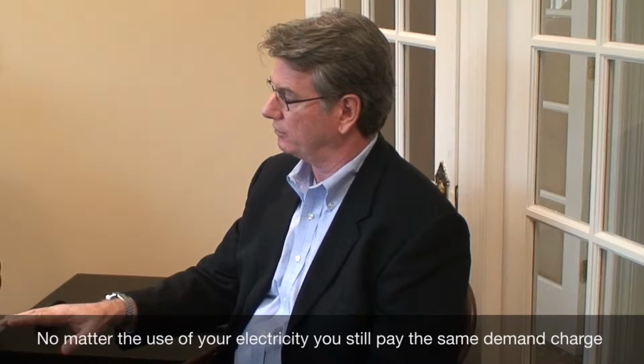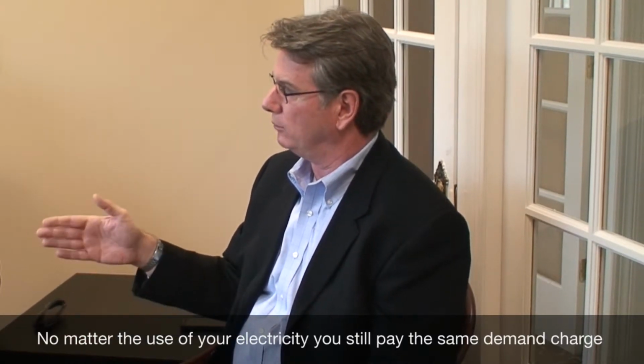Lars, can you explain how batteries can be useful here? There's a couple of different components to your electrical bill. There's an actual consumption charge, but there's also another charge called a demand charge, and that's based on what you're going to demand from that utility, what type of power you potentially have. Demand charges are almost equatable with infrastructure. So for example, when chillers come on during the summertime, you'll have a demand for it at that point, but no demand in the wintertime. But you still need that infrastructure to be able to support those devices. That's something that John and I work on with regards to batteries, is that we look at those demand charges, and then we essentially design a system for battery storage to be able to shave the peak off of those demands.